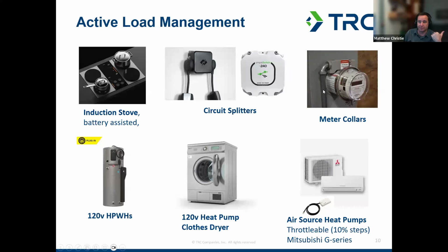So these are often used to feed electric vehicles, and often used to pull in power from solar to avoid having a breaker, a safety breaker, on the meter side if you have solar power being pulled in. But technically they could be used to supply a dryer or a stove, though it's kind of an inconvenient place. So EV is the most common, but similarly, one of your main loads or a big load can be sort of outside of that, summing up to 80.